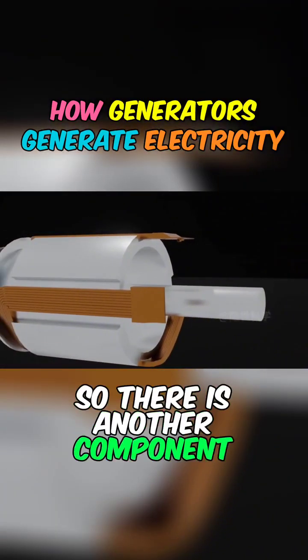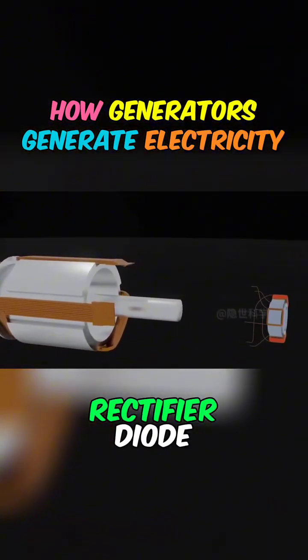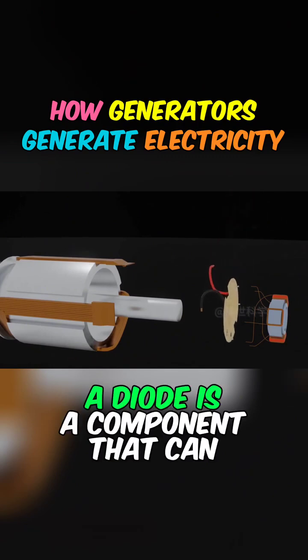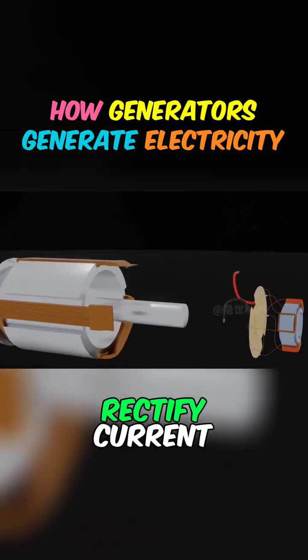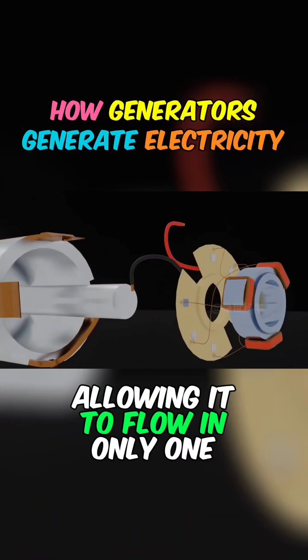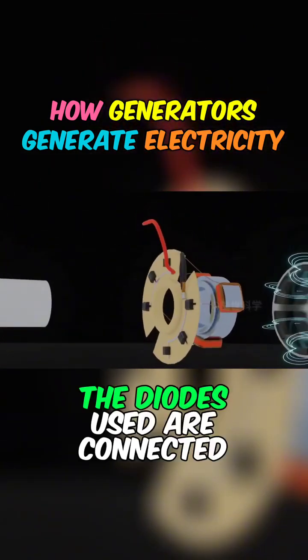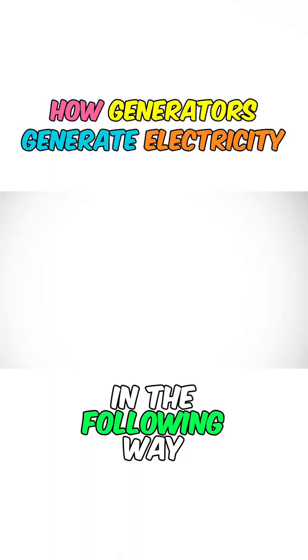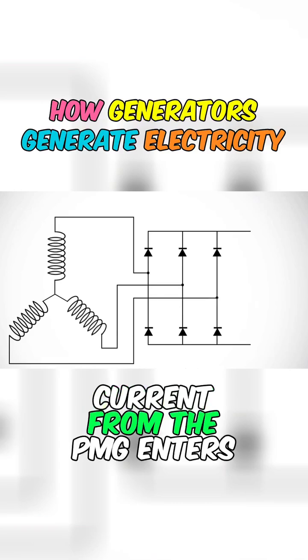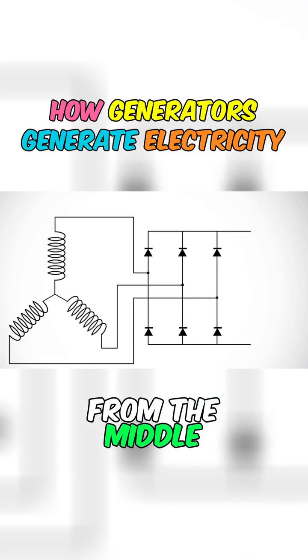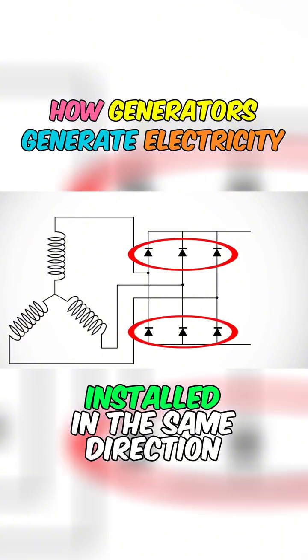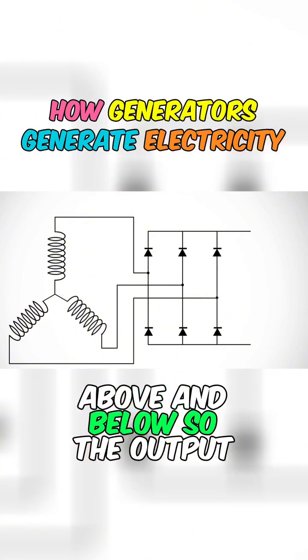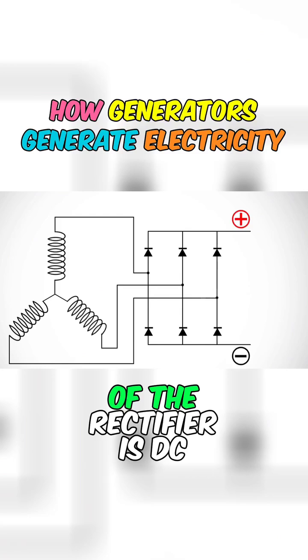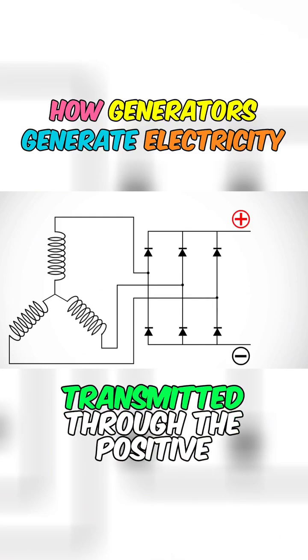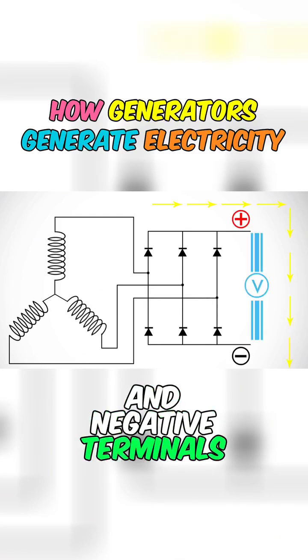So there is another component: the rectifier diode. A diode is a component that can rectify current, allowing it to flow in only one direction. The diodes used are connected in the following way. Current from the PMG enters from the middle, with several diodes installed in the same direction above and below. So the output of the rectifier is DC transmitted through the positive and negative terminals.